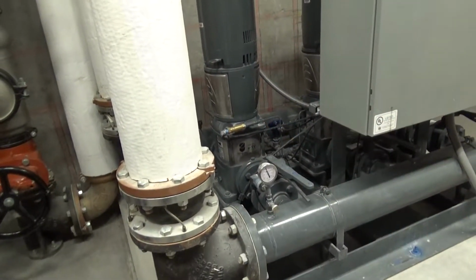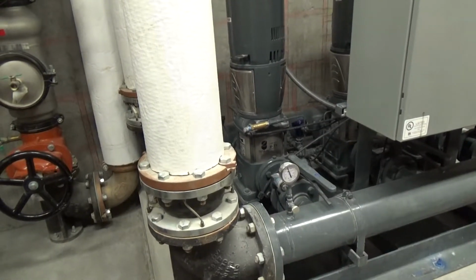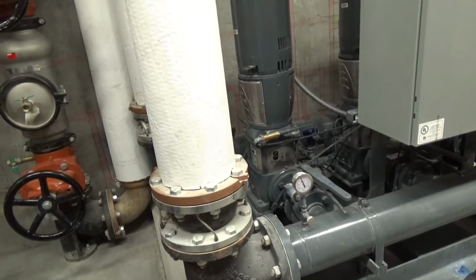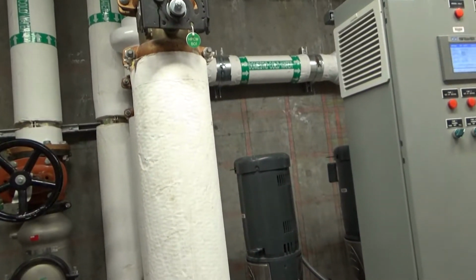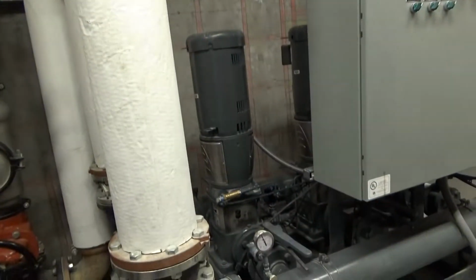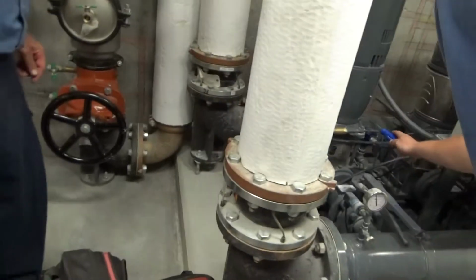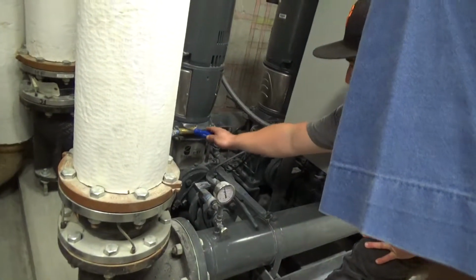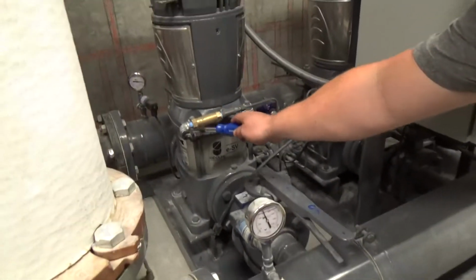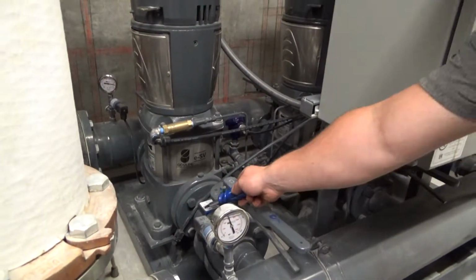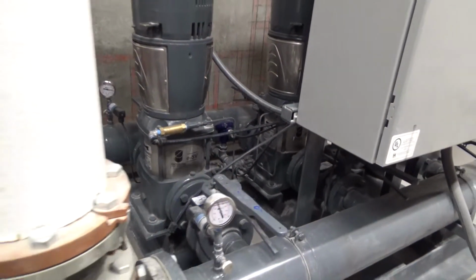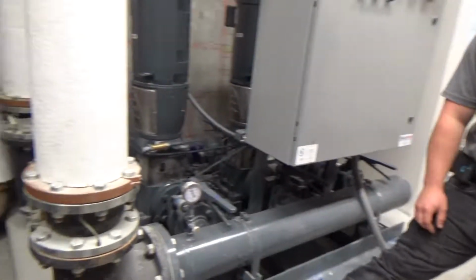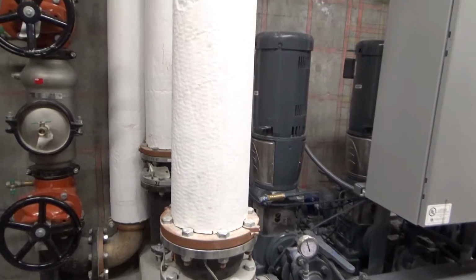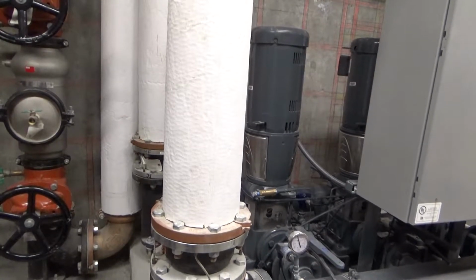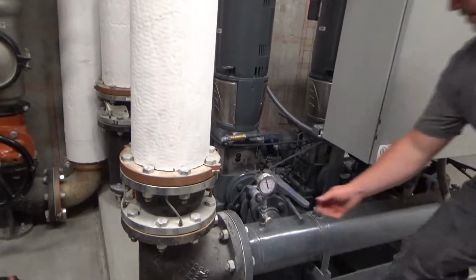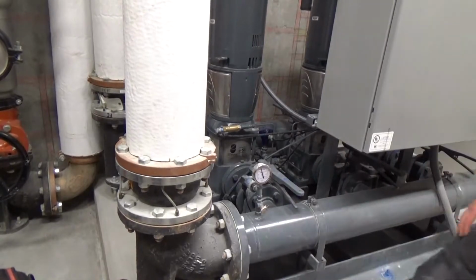That's your temperature and pressure relief valve. So at temperature 130 it'll pop, and pressure 300 psi. So is that tubing just to the drain, or is it like a measurement? This tubing is the one that goes to the temperature sensor, and this is the outlet of that relief valve. If it ever pops, they all link together and go out of that pin right there. So that's kind of like a telltale: if you see that thing squirting out, that relief valve popped or failed. I haven't seen one fail yet, but it is possible. Anything mechanical can fail.